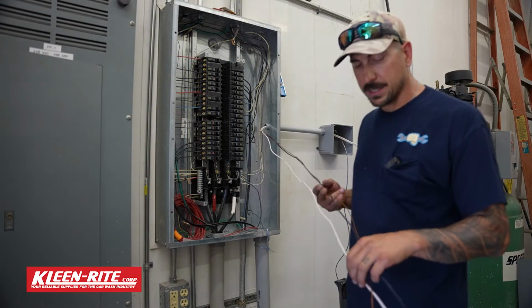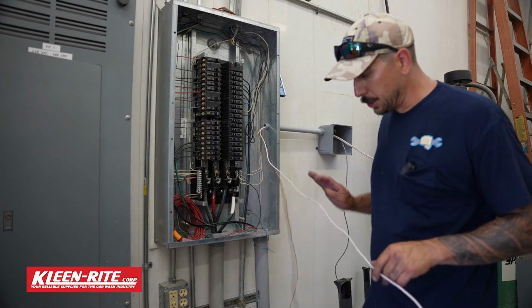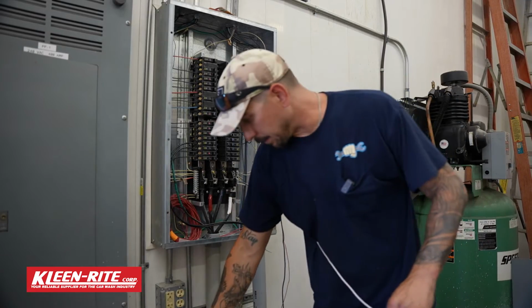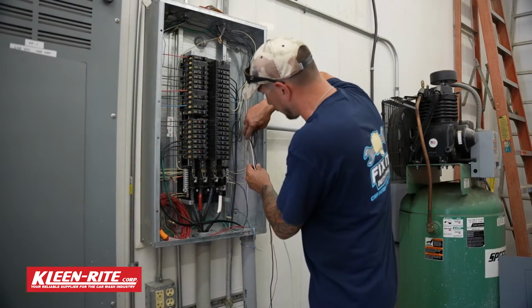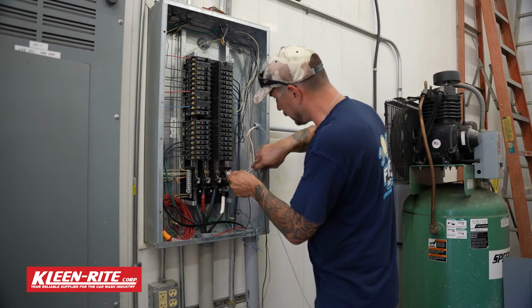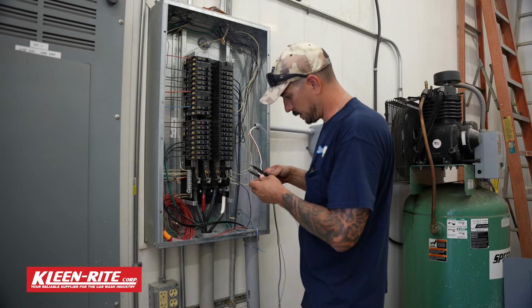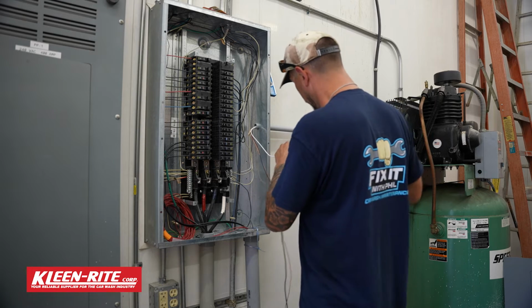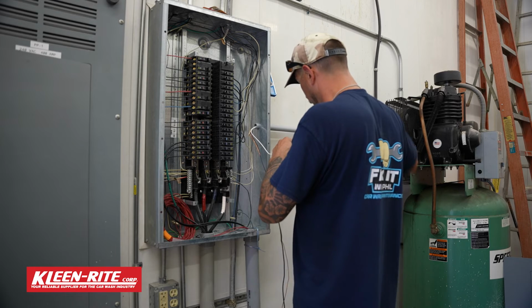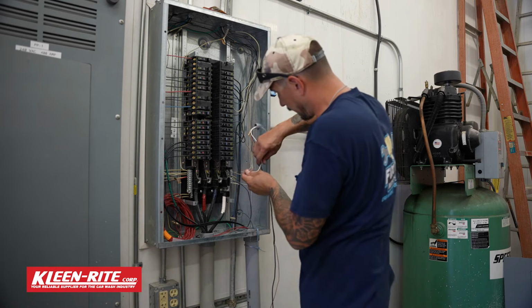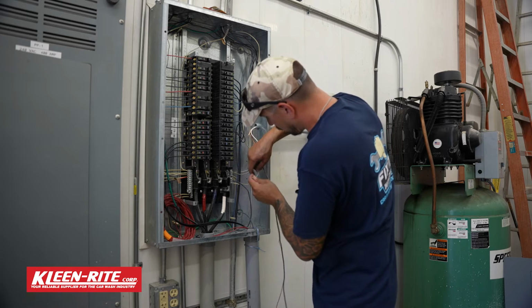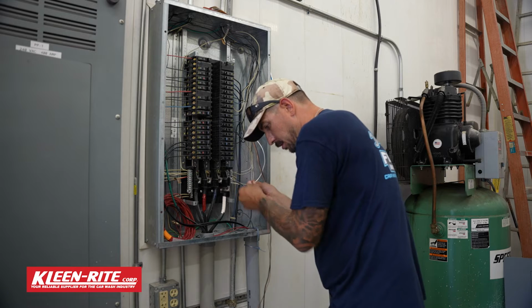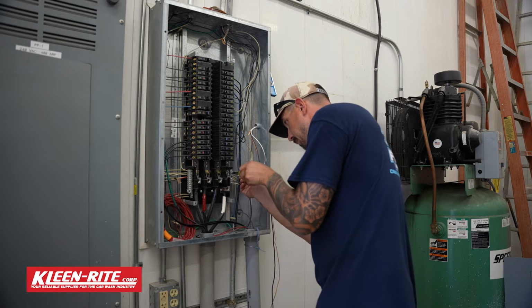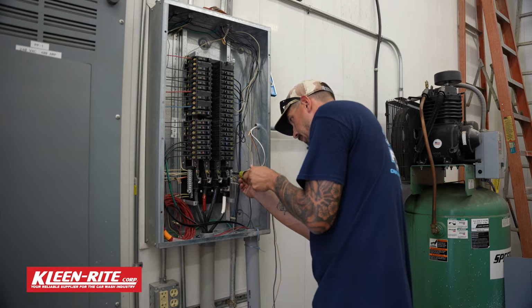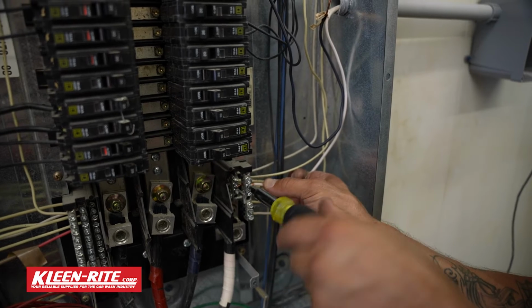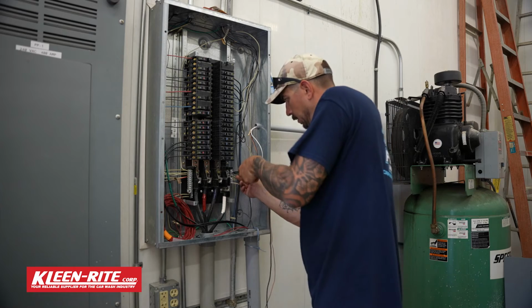So when we're hooking our wires up to the panel, you always want to hook your neutral up first. I typically always hook my neutral up first, and then I'm going to hook my ground up, and then I will hook my hot wire up. So I'm just getting a quick guesstimate length on that. It doesn't need to be perfectly straight. We don't want to pull it too tight. We want to give ourselves a little bit of breathing room when we're doing this. Okay, so now we got the neutral hooked up.